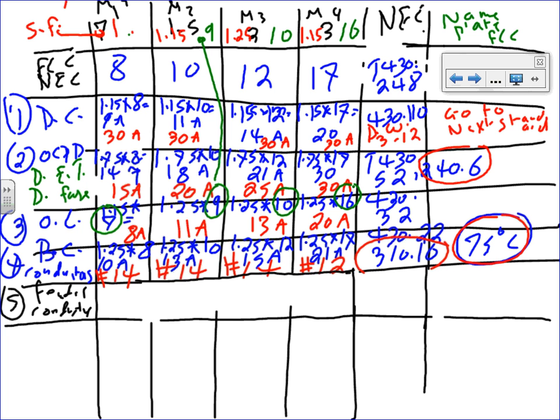When you size the feeder, you're going to go to 430.24, and also 310.16 under the 75-degree column. When you go there, it tells you to take the largest amp motor. Amp, not horsepower. The largest amp motor, which ends up being the largest horsepower motor, but it doesn't have to be. The amps of a motor could be higher and the horsepower lower if you're using single phase and 3-phase motors together, but that's a whole different story. The largest motor amp, what's the largest motor amp?